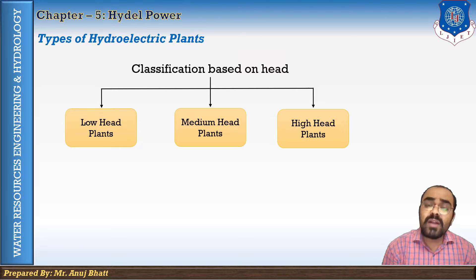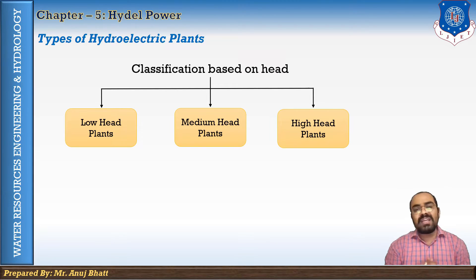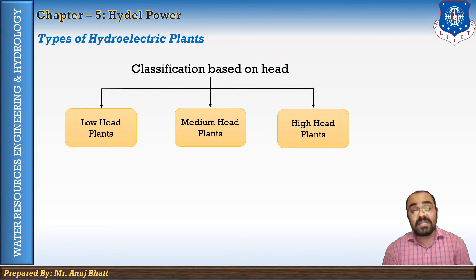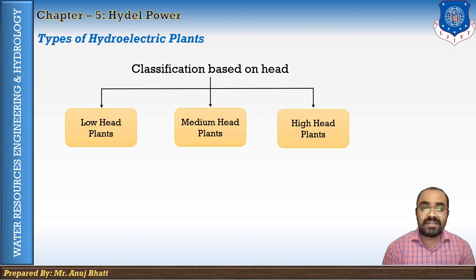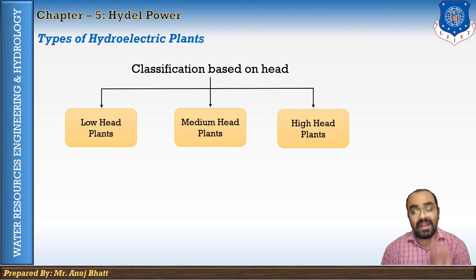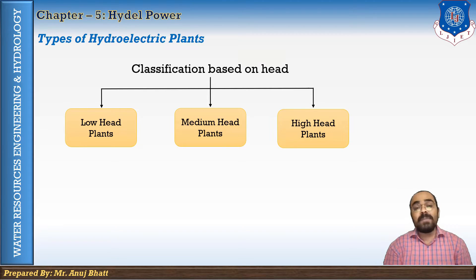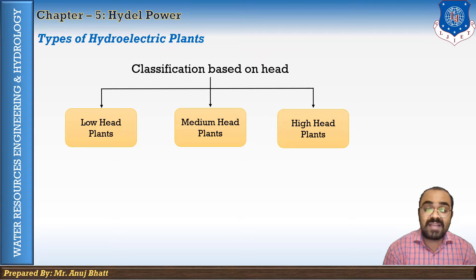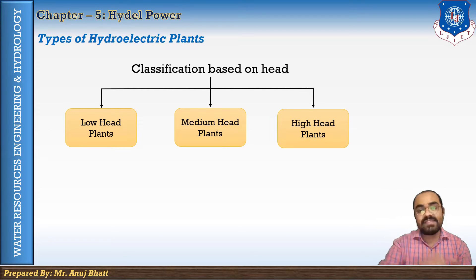Sometimes the barrage is constructed some distance upstream of the powerhouse and water is conveyed to the powerhouse through an intake canal. A medium head plant uses a head between 15 to 60 meters. Such a scheme is essentially a storage scheme where a dam is constructed to store water and obtain the required head. A medium head scheme has features midway between the low head and high head schemes.